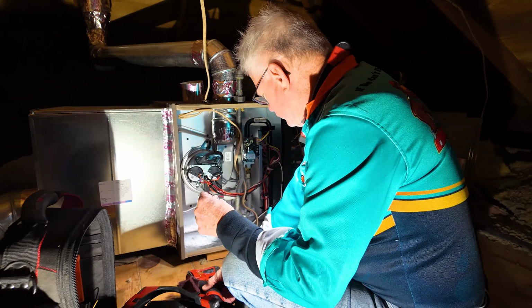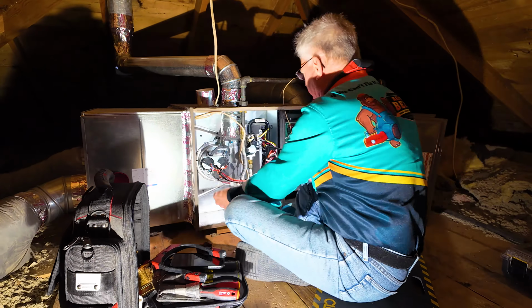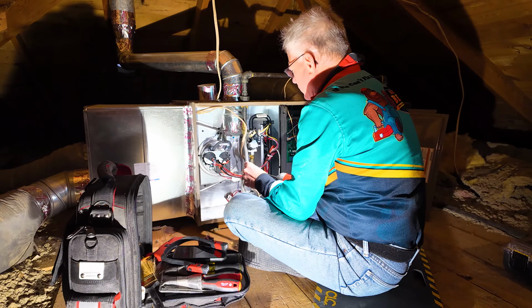And then I'm going to go ahead and do an ignition test, and we'll test a few other things while I'm at it. Just while I'm here, because when you're here on a call, the expense of making the trip and coming out here has been already a sunk cost. So then it's important that you go ahead and do everything you can while you're here, because why not? It's good. Replace the wire.